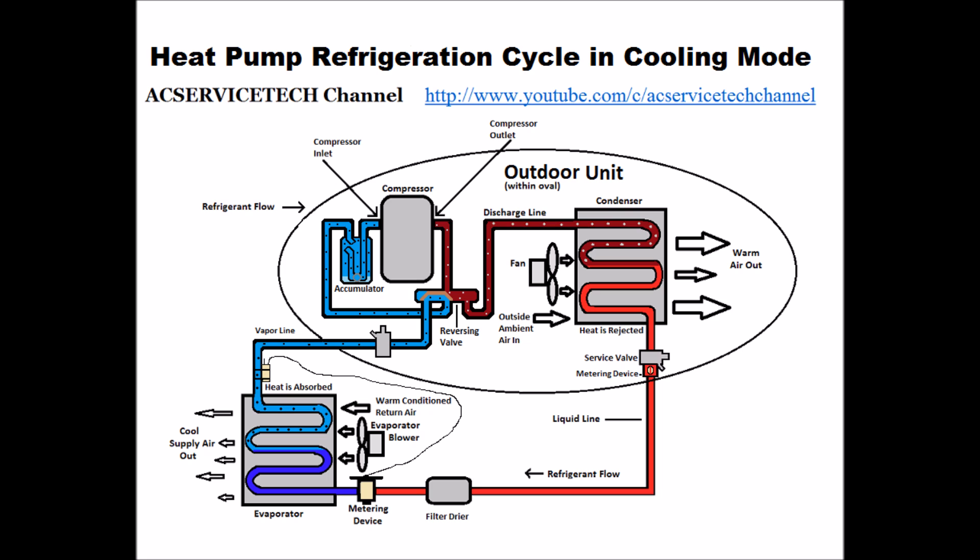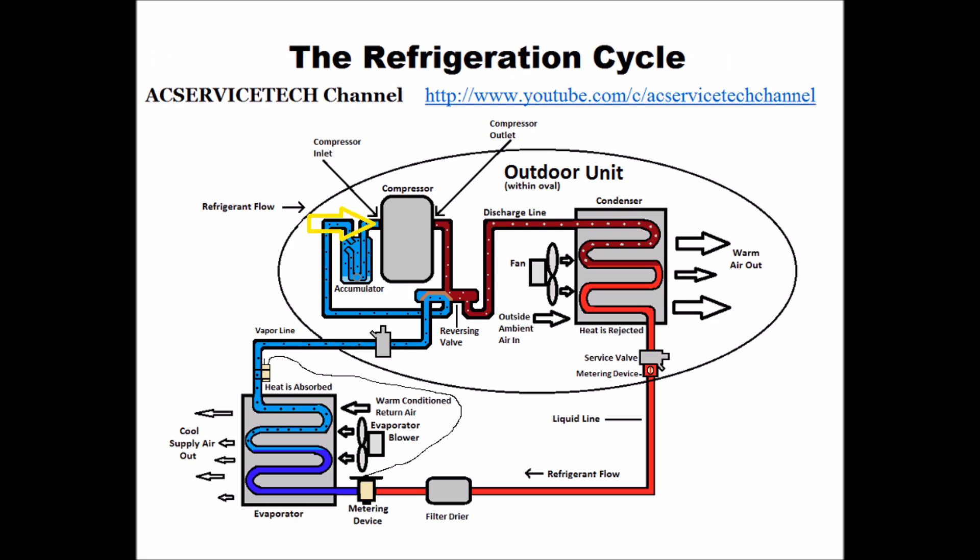Hey guys, this is ACService Tech, and today we're looking at the heat pump refrigerant cycle in cooling mode. We have low pressure, low temperature vapor refrigerant going into the compressor. It then comes out of the compressor as a high pressure, high temperature vapor refrigerant. The compressor's job is to raise pressure, and temperature will follow pressure. So now we have high pressure, high temperature vapor refrigerant at its hottest point in the entire system.